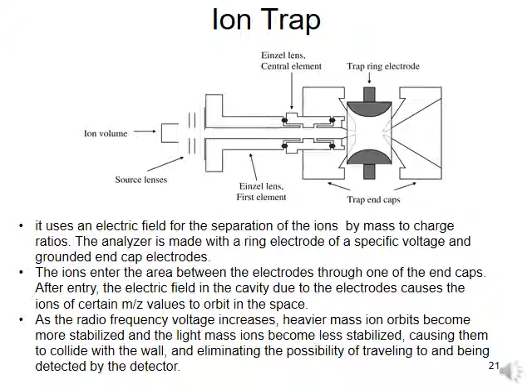The ions enter the area between the electrodes through one of the end caps. After entering, the electric field in the cavity due to the electrodes causes ions of certain mass to charge ratio values to orbit in the space. As the radio frequency voltage increases, heavier mass ion orbits become more stabilized and the light mass ions become less stabilized. So it will cause them to collide with the wall and eliminate the possibility of traveling and being detected by the detector.